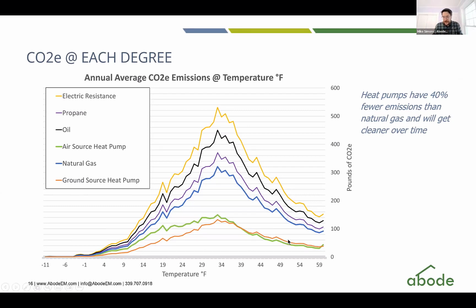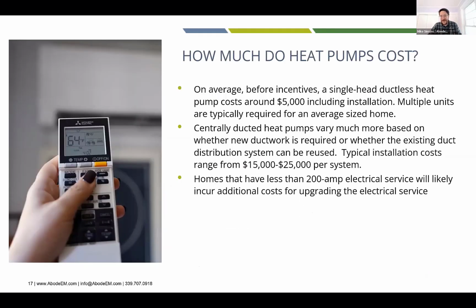The other thing I like about this chart is that it's interesting to see that when it's warmer outside, an air source heat pump can actually be more efficient than a ground source heat pump. If the air temperature is 55 degrees outside, the air source heat pump will be more efficient than a geothermal heat pump pulling energy out of 45-degree ground. I like this crossover point—it confirms that this chart makes a lot of sense.